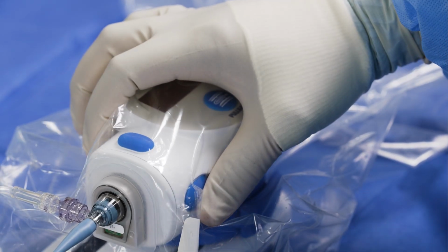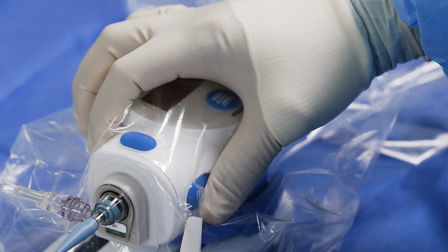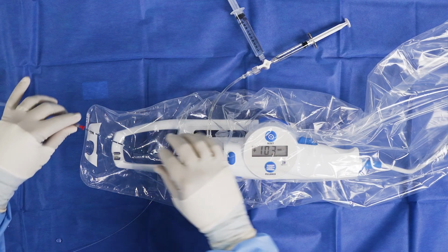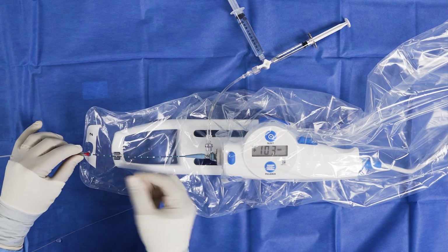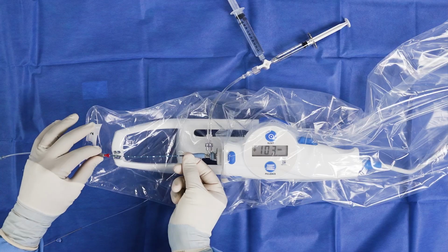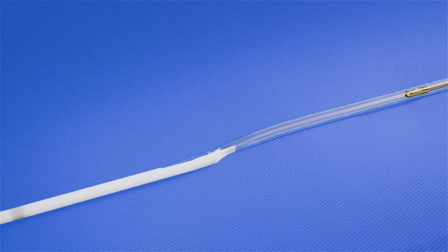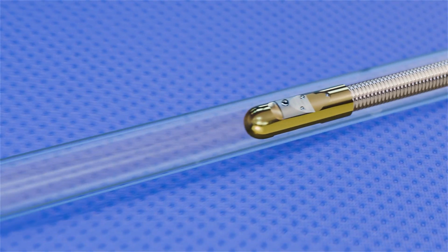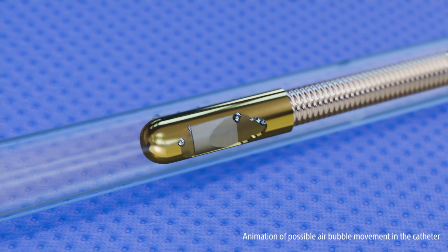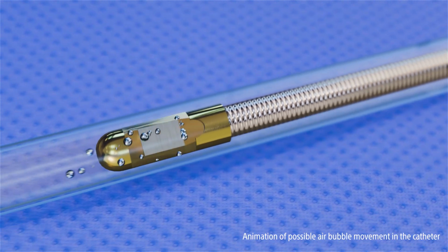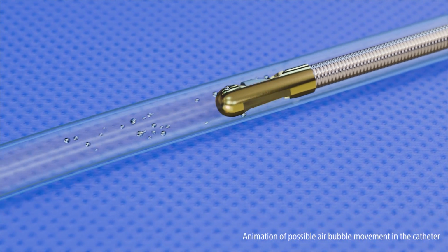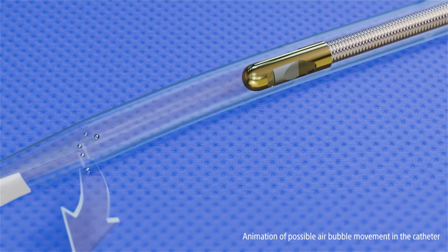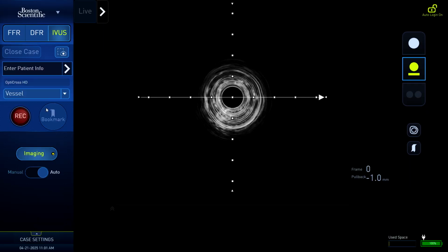Activate imaging by pressing the button on the MDU and then carefully close the telescope using both hands. This step is key to help reduce the occurrence of air bubbles and image dropouts when the catheter is being used. The system will show bright concentric rings, confirming that the catheter is functional.